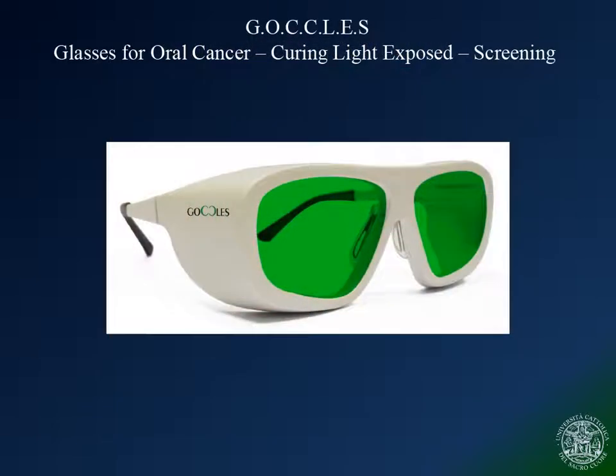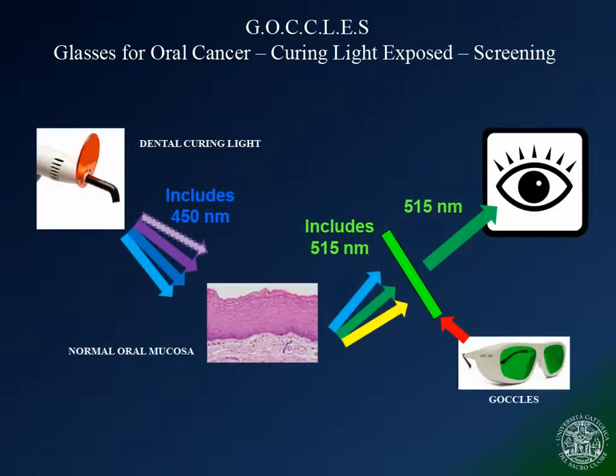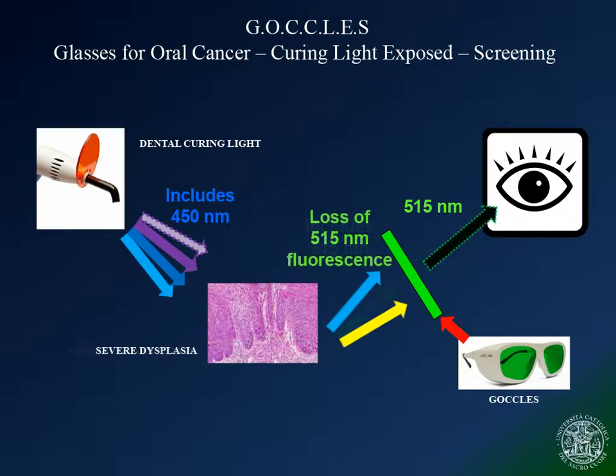The Goccles Medical Device is a low-cost and easy-to-handle medical device for the detection of potentially malignant lesions of the oral cavity in the dental practice setting. It consists of a pair of glasses equipped with filters that highlight autofluorescence when the oral mucosa is irradiated by the light emitted by any dental curing light. Potentially malignant lesions will appear as dark spots on a green background.